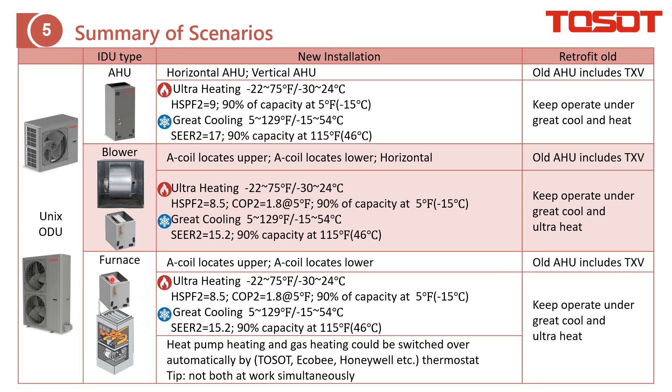The last scenario is unix together with a furnace to achieve dual fuel. The A-coil can be installed at the upper side or the lower side of the furnace, and you can again achieve Ultra Heating and Great Cooling. For dual fuel, we require the thermostat to support the detailed settings. For more detail, please refer to my previous introduction. For retrofit projects, the unit must always include a TXV for cooling.